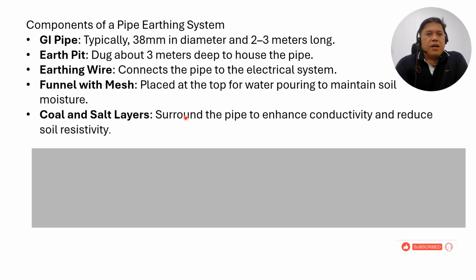So components of the pipe earthing system: number one, GI pipe, typically 38 mm in diameter. Earth pit, that is 3 meters deep, houses the pipe. Earthing wire connects the pipe to the electrical system. Funnel with mesh is placed at the top for maintenance, for pouring water to maintain the soil. We have different soils that we are using, guys, and I will share this with you in a later stage of my presentation.